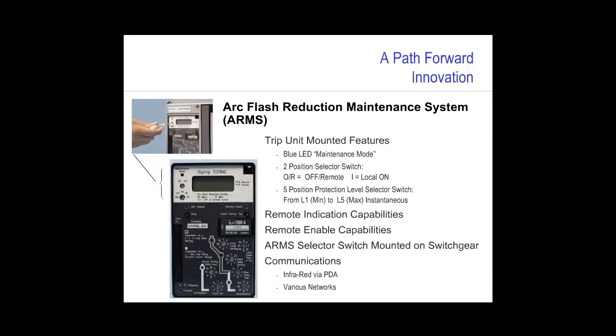breakers. The Eaton offering here is called ARMS, Arc Flash Reduction Maintenance System. This actually is an option on low and medium voltage integral trip units for circuit breakers. And you can see in this picture that we have, in the upper left-hand corner of the integral trip unit, the capability of turning on a maintenance mode and selecting 5 different instantaneous settings.